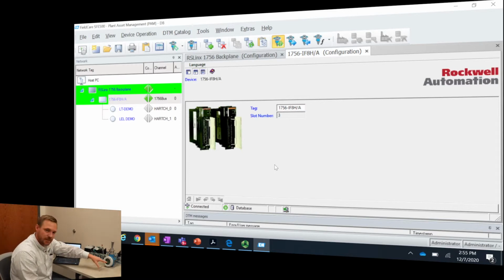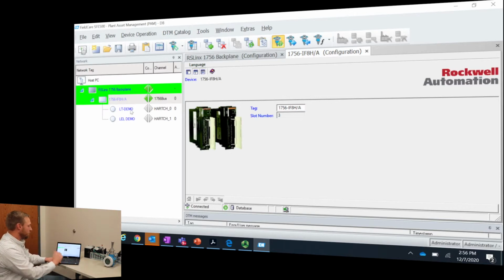Both these devices are just sending out a milliamp signal to input points on this card, and superimposed on that milliamp signal is a HART signal. HART is fairly robust. However, it takes a long time for it to transfer data, and that's why it's not instantaneous. It takes a little bit of time for all the information from each of these to pull into the card. All right, so it pulled up both of our devices.